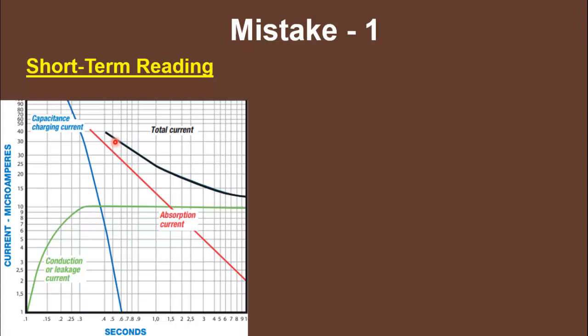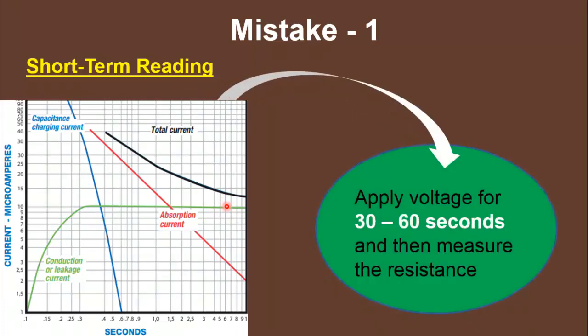At the start of the test voltage, the amount of current is very high, so you see a low resistance value on the Megger. As time passes, this current settles down and reflects only the true leakage current. Therefore, to take a correct reading, we must apply the voltage on the equipment for 30 to 60 seconds before measuring the resistance, otherwise you will get an incorrect value.